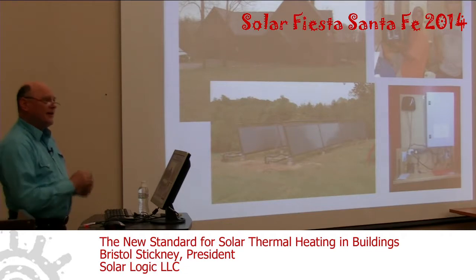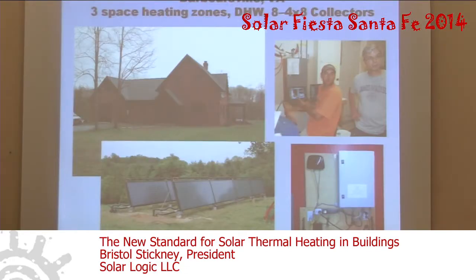Here's another building. This is the third example I'm going to show you before I start talking about how we do this new standard. This is a house that we retrofitted in Virginia, about a 2-hour drive from Washington, D.C. Yes, it's still cold enough there to require heating, and this is just an ordinary suburban house with radiant heated floors in it, and it already had a boiler heating the floors with warm water, and the boiler runs on fuel oil. And fuel oil is just as expensive to buy as propane is these days. So the homeowner was interested in cutting his fuel oil consumption.